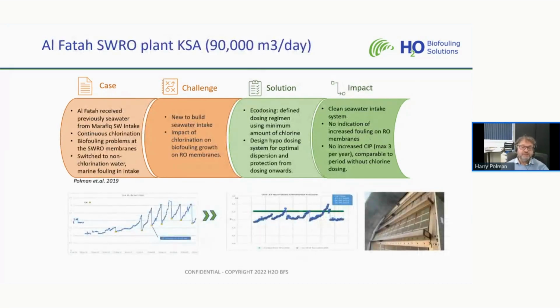A seawater RO plant in Saudi Arabia started the plant in 2012, first of all with seawater which was continuously chlorinated. They neutralized it with sodium bisulfite, but they saw a lot of bacterial fouling on the RO membranes. So they switched to a system where there was no chlorination in the seawater intake. The quality of the membranes improved. The cleaning frequency was postponed from every 30 days with continuous chlorination to about every 3 months. But then they saw that there was marine fouling in the intake pipes and also in the pre-filtration system.